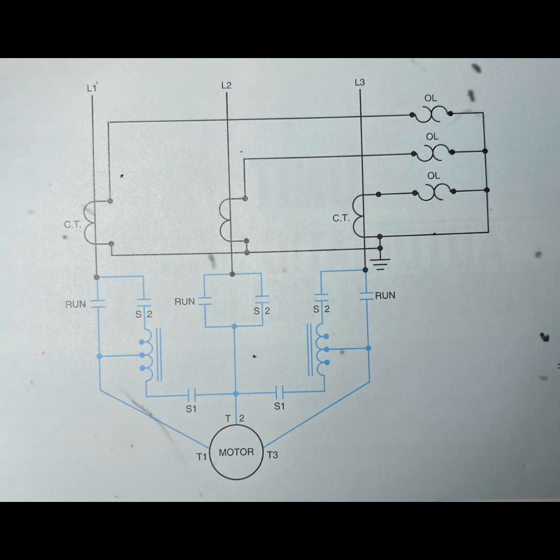For the closed transition starter, the starting contactors consist of a 3-pole contactor and a 2-pole S1 contactor, operating independently from each other. During the transfer from start to run, the 2-pole contactor is open and the 3-pole contactor remains closed. The motor continues to accelerate with the autotransformer serving as a reactor. With this type of starter, the motor is not disconnected from the line during the transfer period. Thus, there is less line disturbance and a smoother acceleration. The autotransformers are de-energized while in the running position. This is done to conserve electrical energy and to extend their life.